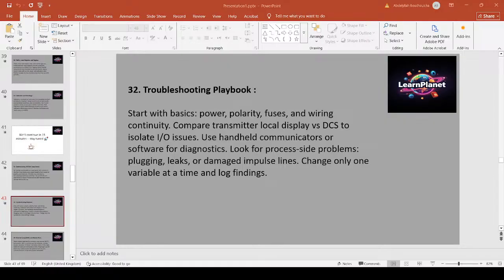Change one variable at a time. Log steps and revert if no improvement. Example: when a DP filter reading jumps, isolate and blow down impulse lines to remove trapped air pockets before changing transmitter setting.